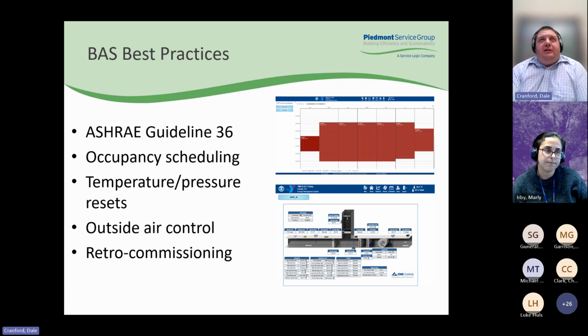Another best practice that we try to implement everywhere we can, where you don't have a 24/7 operation, is occupancy scheduling. So you only want to schedule your HVAC systems to be in operation when there are people in the building. But you do want to be careful with that too, making sure that you're using some kind of optimization sequence, or maybe turning the systems on early to make sure that buildings are at set point by the time people arrive.